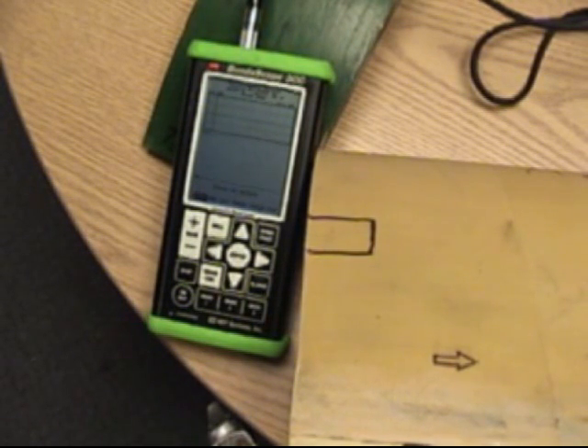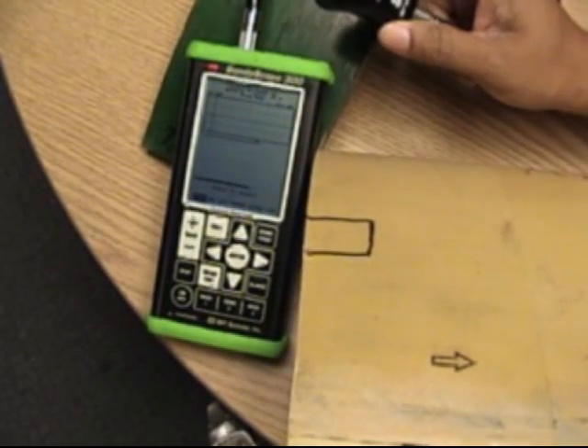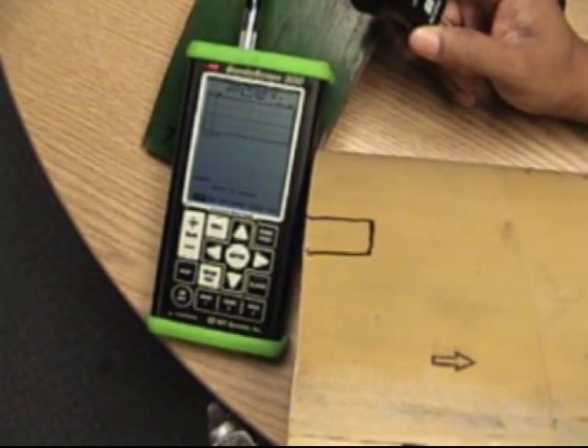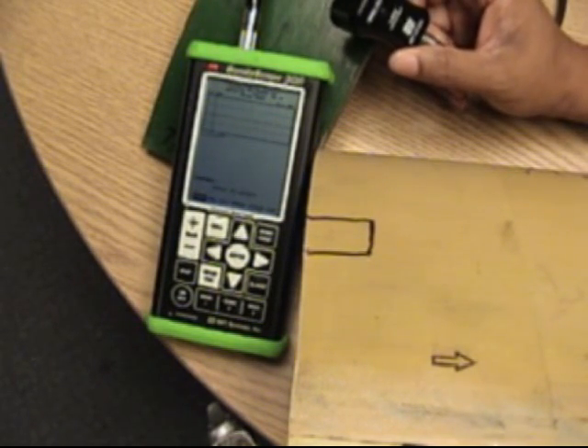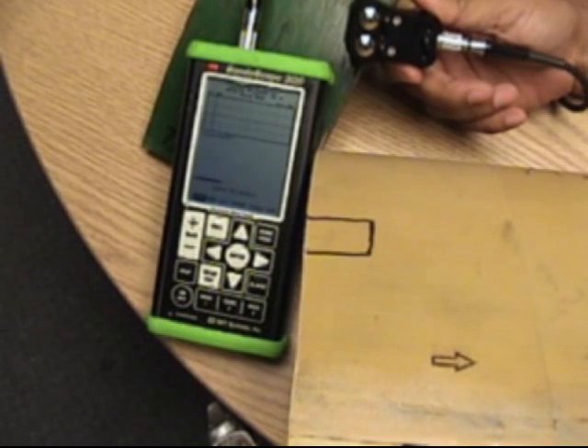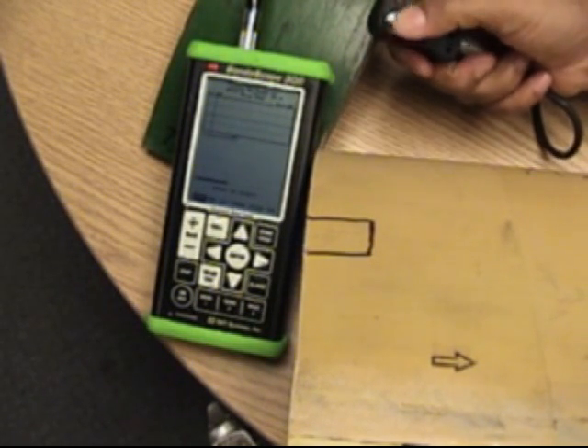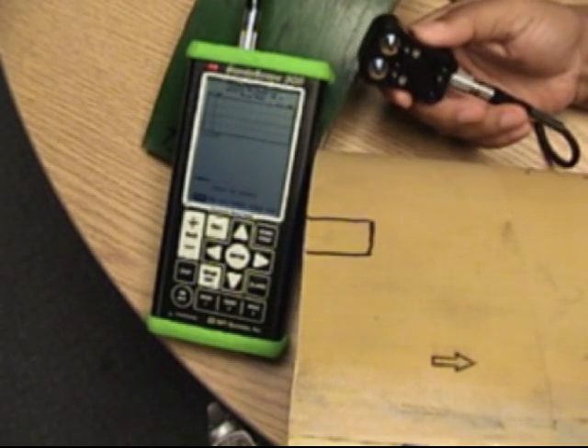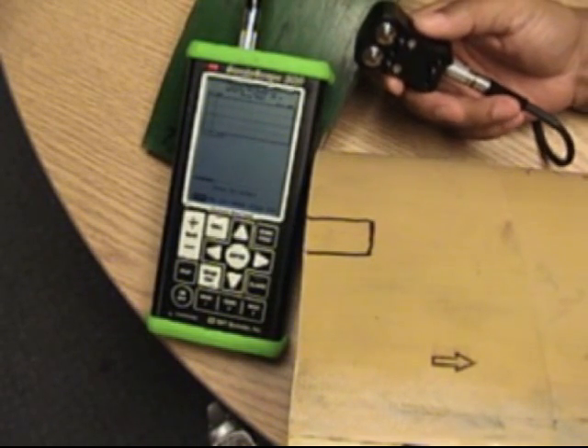So what I'm going to do basically is show you using the Bondoscope 300 in the pitch catch mode with our low frequency probe. You notice it's a probe that has two spring loaded pitch send receive ends on them that will be placing on the part.